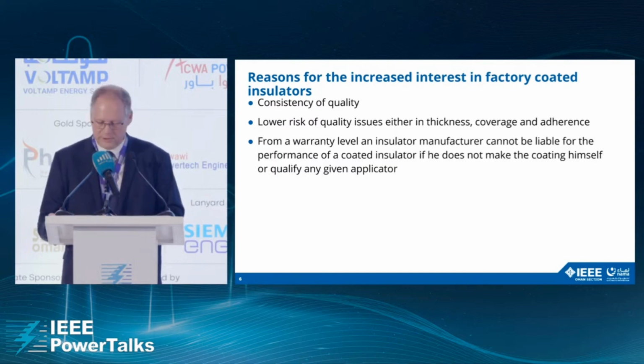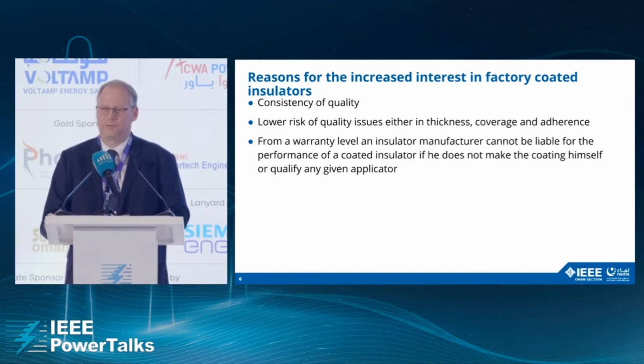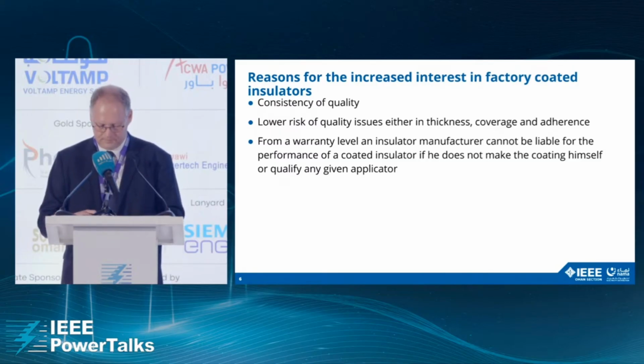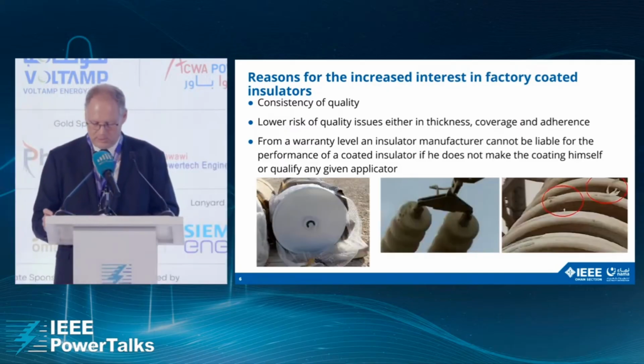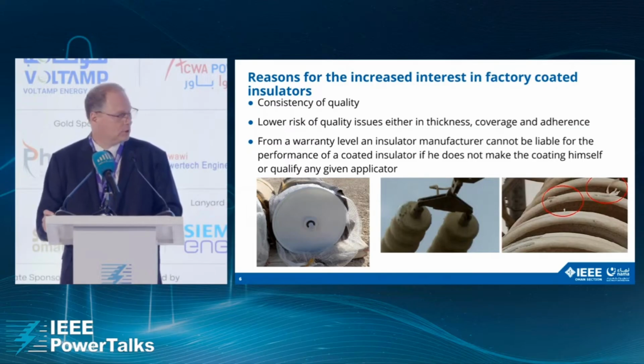The product is no longer defined as a coating, but as a factory coating resulting from the association of an insulator itself, a silicone coating material, and an application process, and the whole being under the responsibility of the insulator manufacturer. Here are some examples of quality defects observed on lines and on insulators that were not coated in a factory, where you may have some inconsistent thickness and lack of adherence.